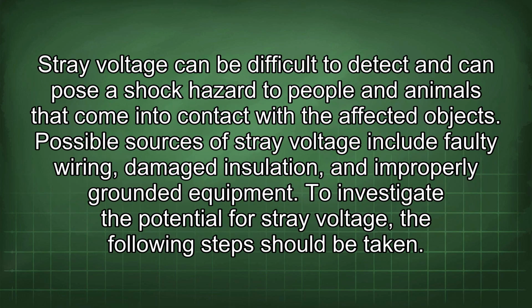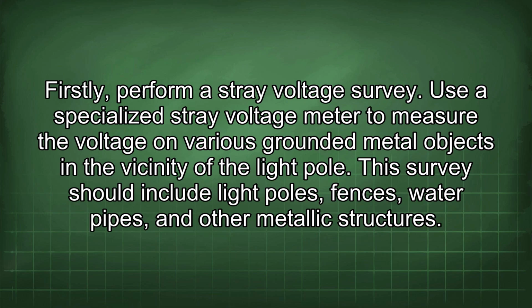Stray voltage can be difficult to detect and can pose a shock hazard to people and animals that come into contact with the affected objects. Possible sources of stray voltage include faulty wiring, damaged insulation, and improperly grounded equipment. To investigate the potential for stray voltage, the following steps should be taken. Firstly, perform a stray voltage survey. Use a specialized stray voltage meter to measure the voltage on various grounded metal objects in the vicinity of the light pole. This survey should include light poles, fences, water pipes, and other metallic structures.